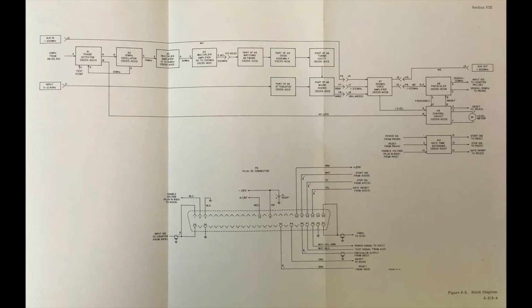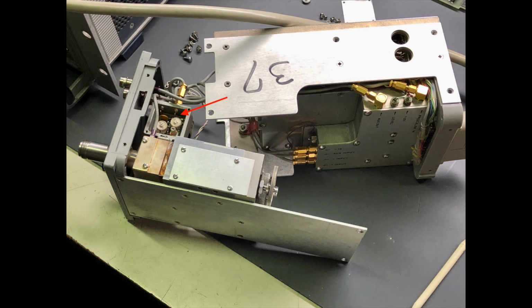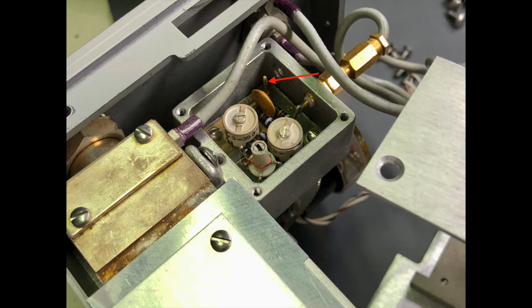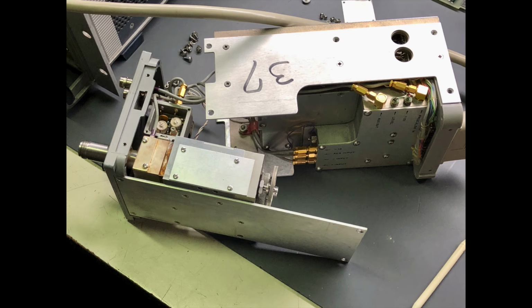Then I realized there's a simple test of the step recovery diode in assembly A5. Just check for -5 to -12 volts DC at test point number 1 in A5. So I decided to do this next. Well, it measured -2 volts DC bias, and then testing with the oscilloscope showed a very low level 200 megahertz signal at test point 1. So it looked like the trouble was with the 200 megahertz generator, or a step recovery diode problem.